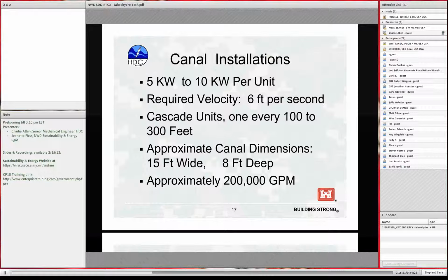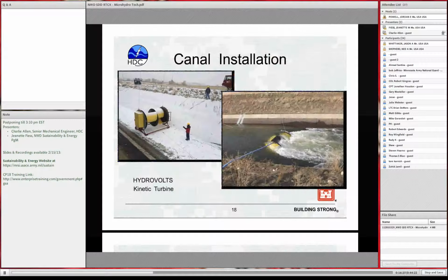This depends on your canal geometry. You need a water velocity in the canal of about 6 feet per second, and the canal can't be small—something on the order of 15 feet wide by 8 feet deep, with a flow rate on the order of 200,000 gallons per minute. Here you see the first prototype installation of a hydrokinetic turbine in a canal in the United States, installed about 18 months ago.